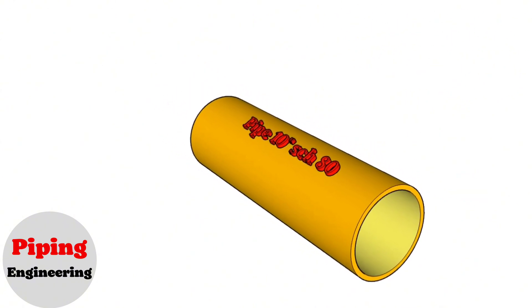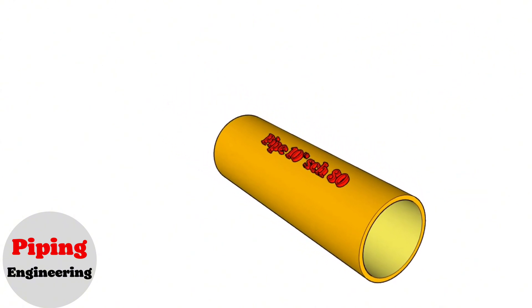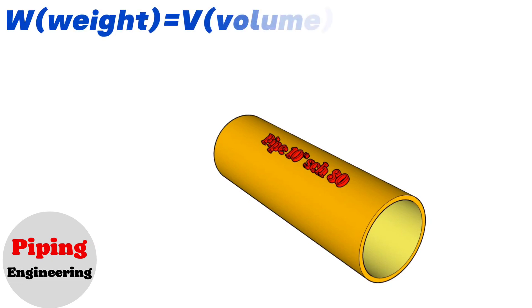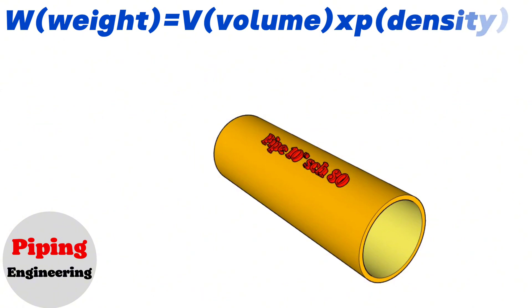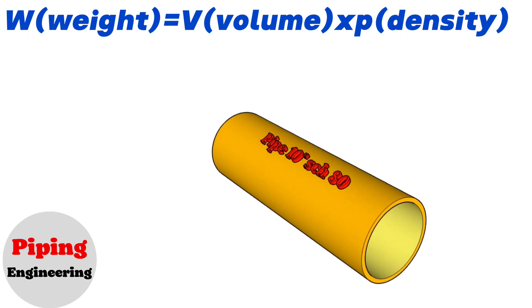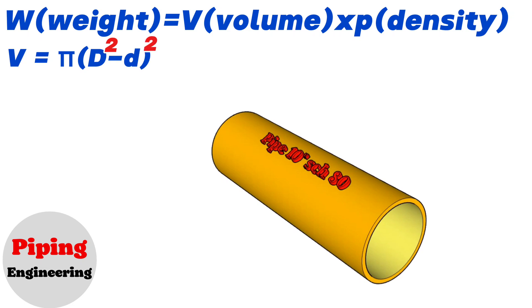Let's start our education video. The formula for finding the weight of the pipe is: Weight equals volume multiplied by the density of the pipe material. The density of the material is taken from the density chart of the materials. We have to calculate the volume ourselves using this formula: Volume equals π multiplied by (outside diameter squared minus inside diameter squared), divided by 4, multiplied by the length of the pipe.